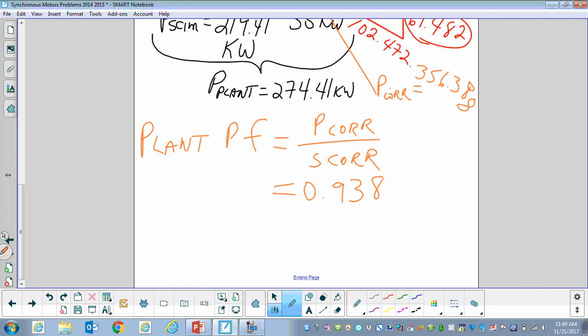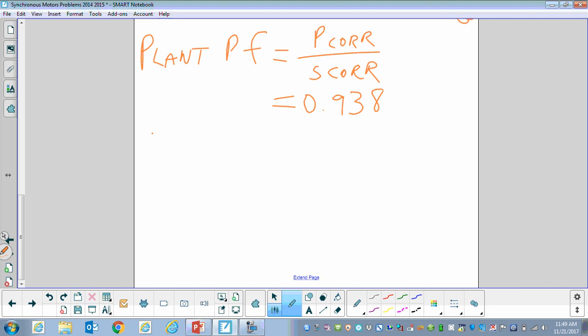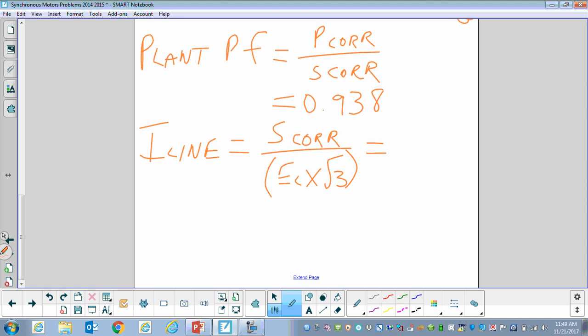And most importantly, this is the key number: what does the company get billed on? We need to know what's my I line, what's the plant now drawing after we've made this correction? We take S corrected and divide that by E line times the square root of 3, since we're dealing with three-phase. Done correctly, it should come out to 356.626 amperes.